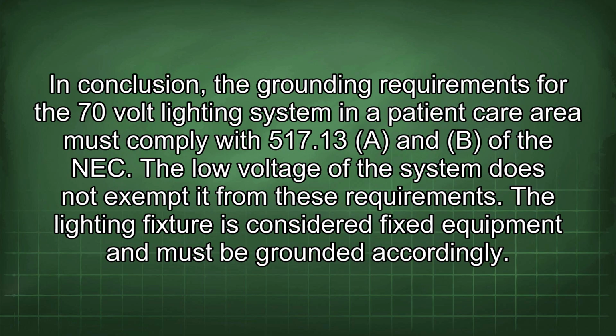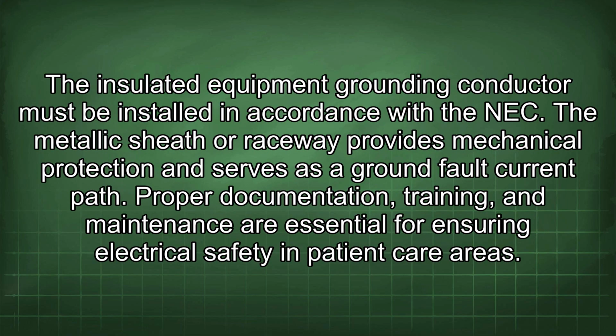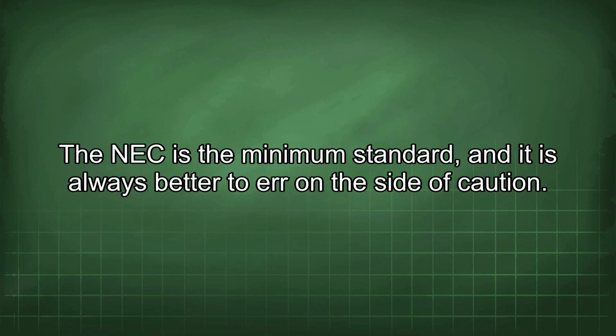In conclusion, the grounding requirements for the 70-volt lighting system in a patient care area must comply with 517.13 of the NEC. The low voltage of the system does not exempt it from these requirements. The lighting fixture is considered fixed equipment and must be grounded accordingly. The insulated equipment grounding conductor must be installed in accordance with the NEC. The metallic sheath or raceway provides mechanical protection and serves as a ground fault current path. Proper documentation, training, and maintenance are essential for ensuring electrical safety in patient care areas. The NEC is the minimum standard, and it is always better to err on the side of caution.